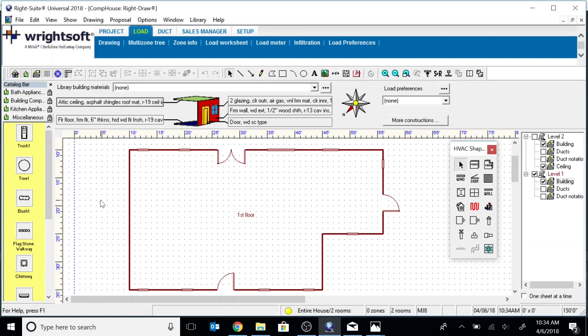In this video, I'm going to walk you through a heat load calculation on my 1984 1000 square foot per ton house. The goal for this video is to debunk the 500 square foot per ton myth when sizing equipment. What I've done is a heat load calculation using Wrightsoft on my own house, just a block load. I'm going to show you all the properties I use just to prove that I'm not fudging anything, and we'll see what the outcome is.